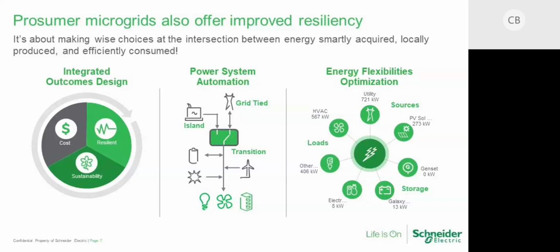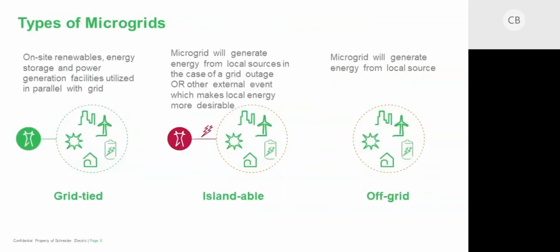And that's what we want to do. On the right-hand side, you just see one of those snowflake charts, where we control all the different loads and generation assets, and it gives us a real-time view into how we're going to manage this. When we look at the different types of microgrids, we typically refer to three different kinds. On the left-hand side, which is probably where we operate most of the time, these are grid-tied.